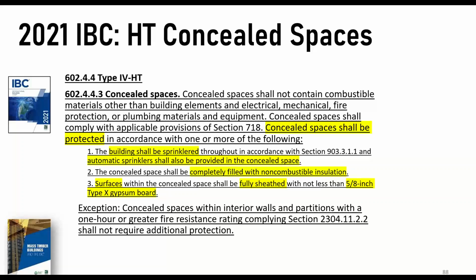Those concealed spaces have to comply with either the sprinkler provisions or be completely filled with non-combustible insulation, or those surfaces, ductwork, chases, and the like, have to be fully sheathed with not less than 5/8 type X gypsum wallboard, which is good for 40 minutes. So if we have a small fire in a combustible chase or some ductwork, it has to be lined, not the ductwork, but the chase itself, the concealed space has to be lined with 5/8 type X gypsum wallboard, which is good for 40 minutes.